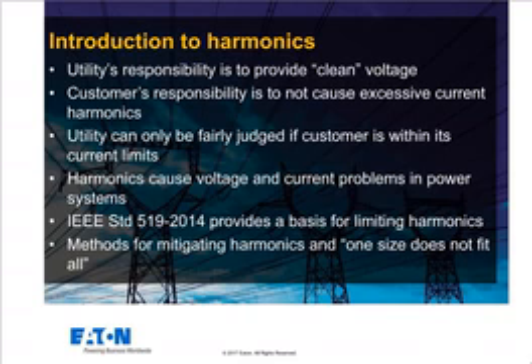So when we look at the basic part and we deal with harmonics, we have to talk about the fact that the utilities are responsible to provide us with clean voltage, but it's the customers' or the end user's responsibility not to put excessive harmonic current back in the system, because what that does is it then corrupts the rest of the system for other users. That could be the total system, or it could be a subsystem within a customer's site themselves.